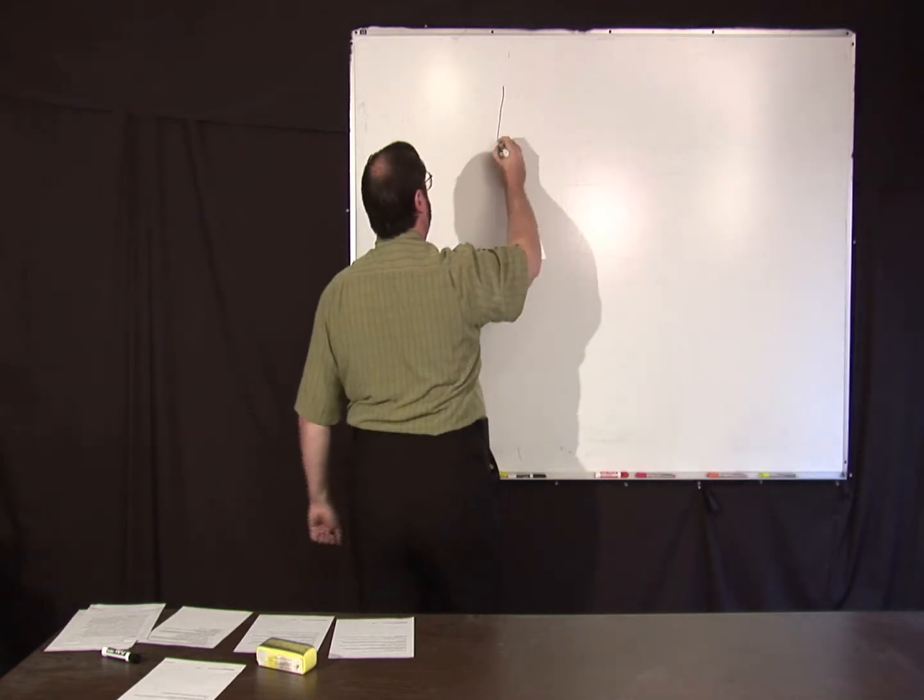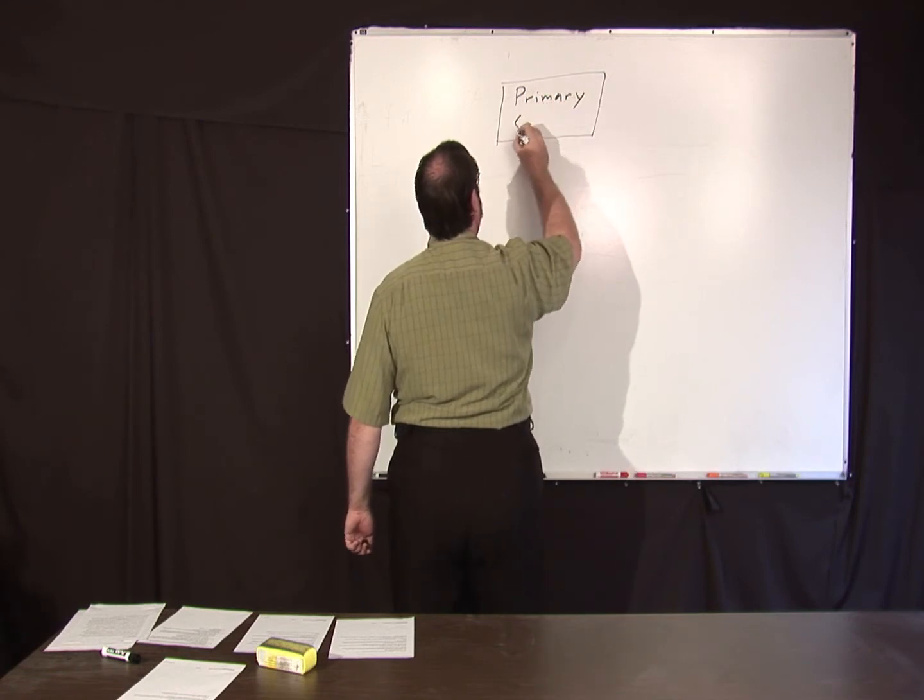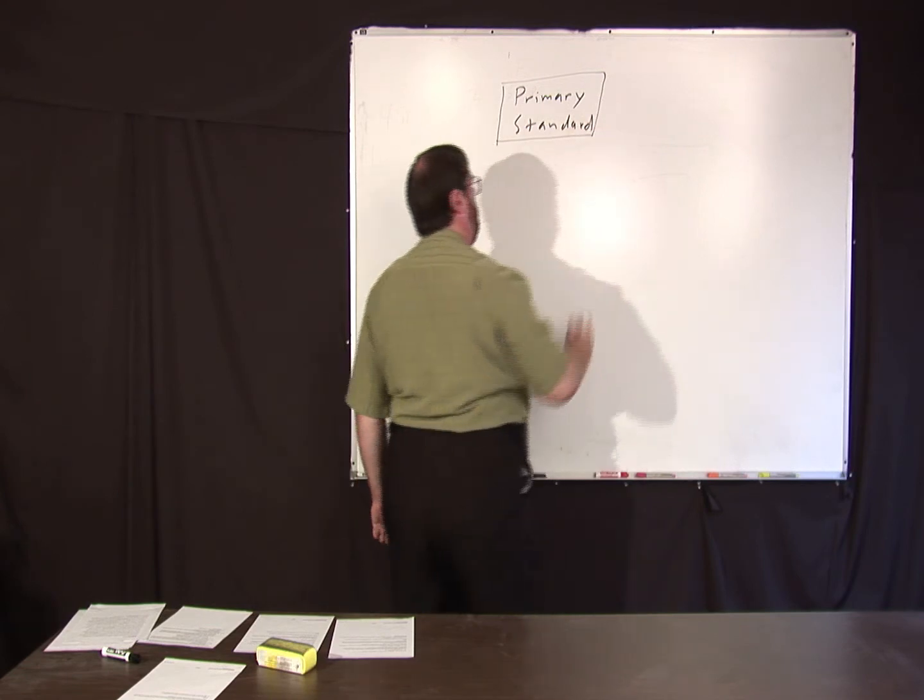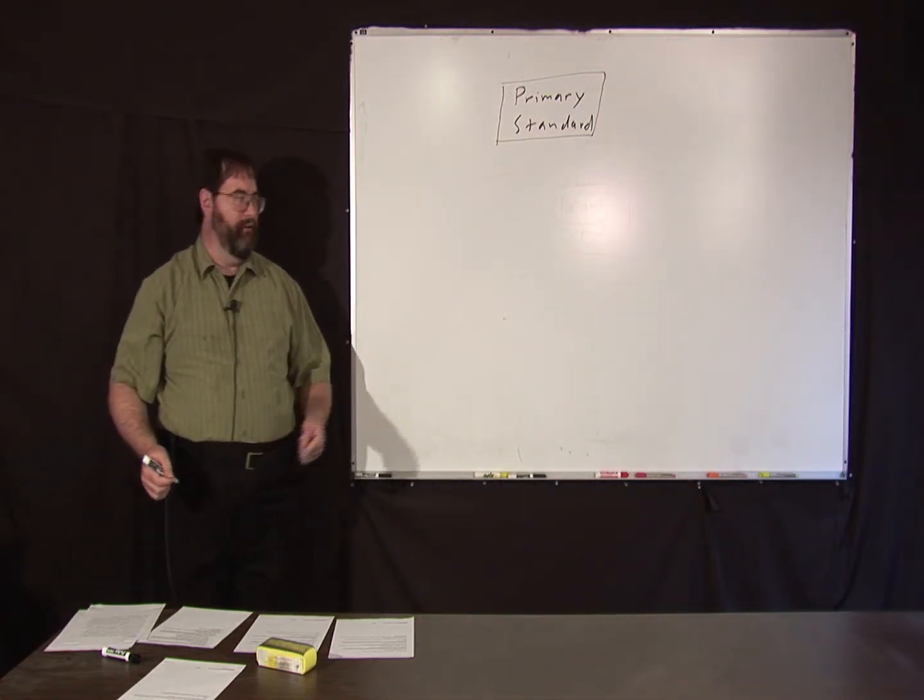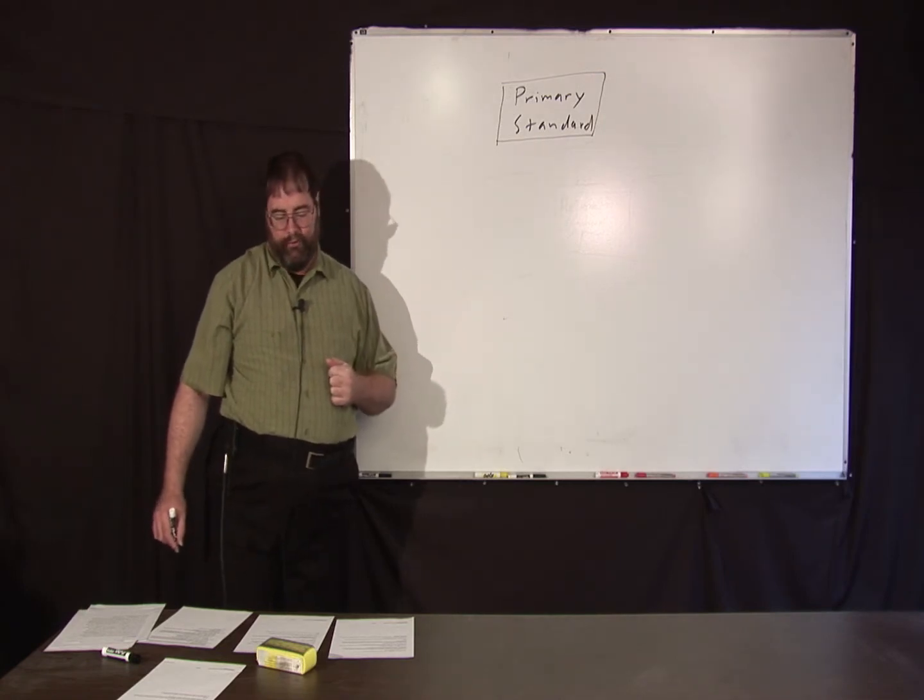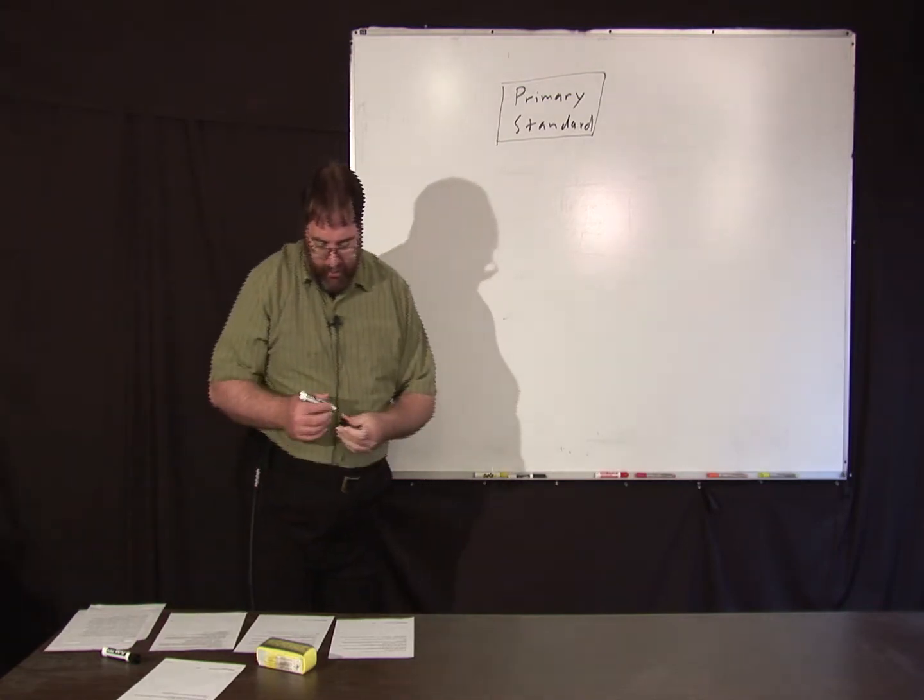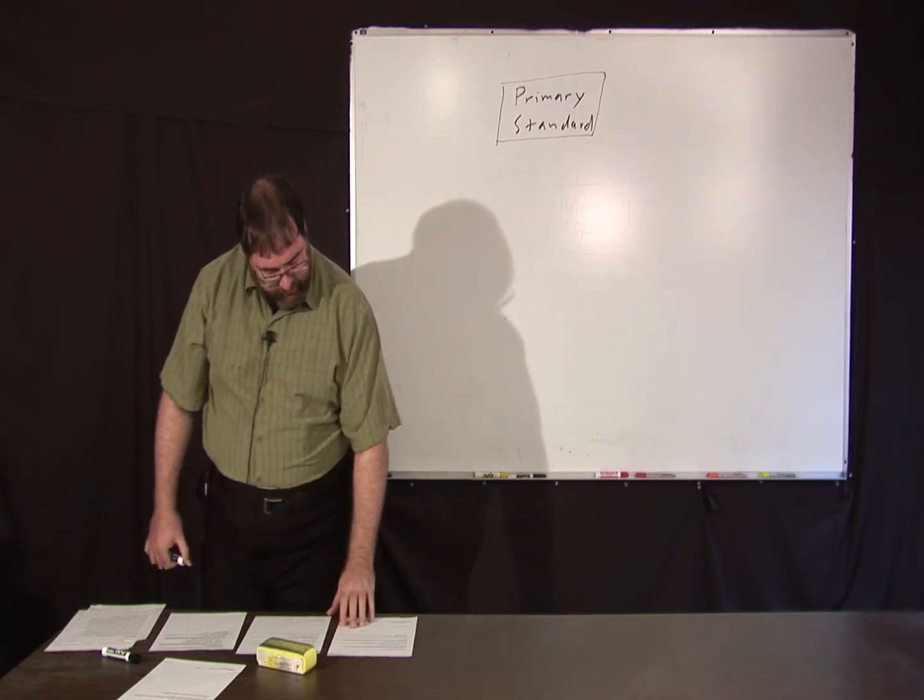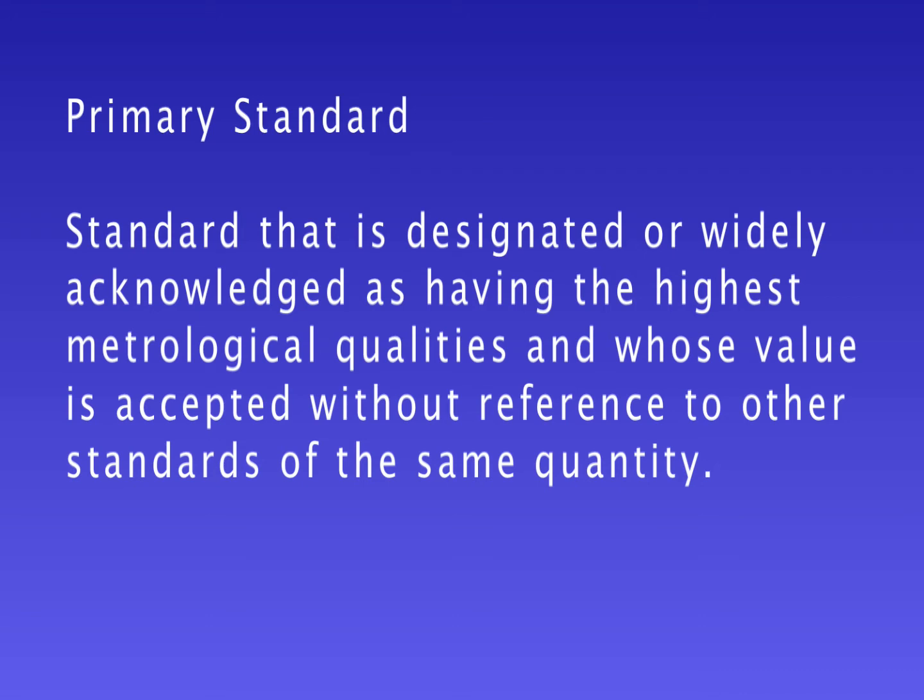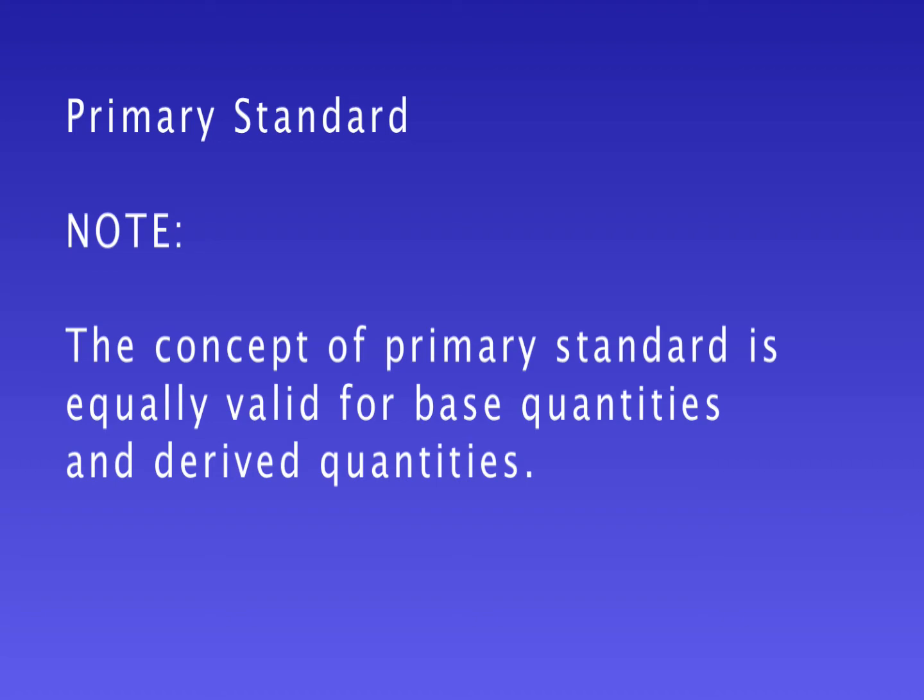We'll talk about primary standards. You can have a primary standard. And it may or may not be traceable back to an international standard or a national standard. For instance, it could be something like Josephson Junction voltage standards, a quantum Hall effect resistor. It could be some other thing that's traceable through natural physical constants or direct realization of the SI units. And a primary standard is defined in the VIM as a standard that is designated or widely acknowledged as having the highest metrological qualities and whose value is accepted without reference to other standards of the same quality. It has a note. The concept of primary standard is equally valid for base quantities and derived quantities.